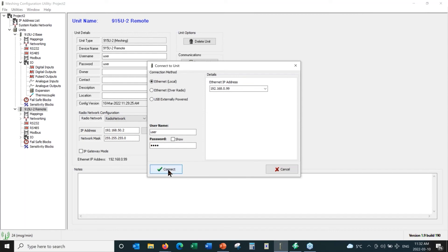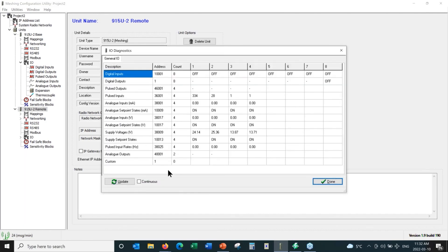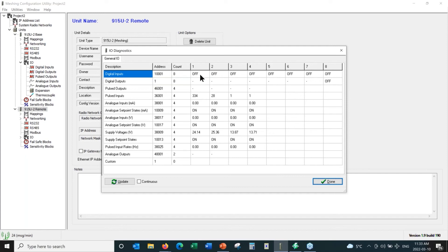Next we're going to see if we can read some of the I/O points on this radio. I don't have any signals wired into the radio right now, so analog inputs one through four are all showing zero milliamps. We can also see the power supply voltages — the main power supply, the analog output, the battery voltage, and the voltage on the I/O expansion module. We can see the digital inputs are all set to off at the moment. If I take a jumper wire across any of the DI's to ground, you will see them turn on.